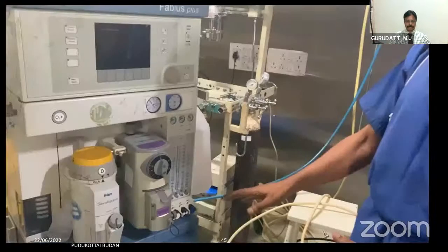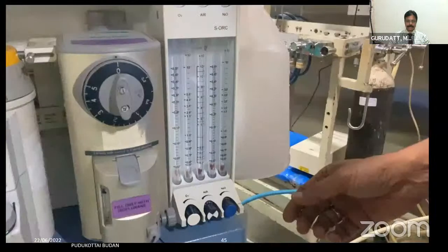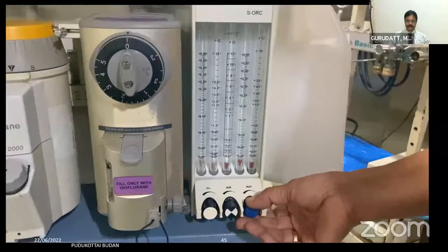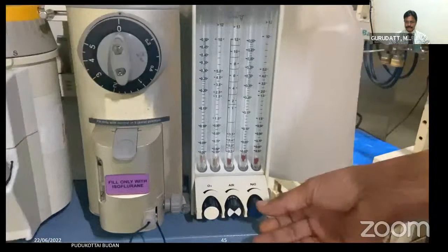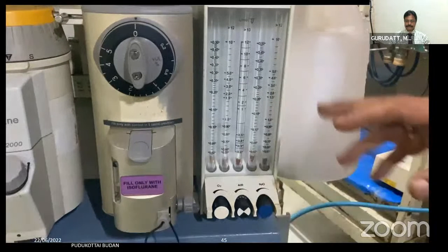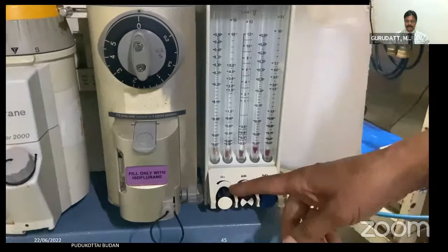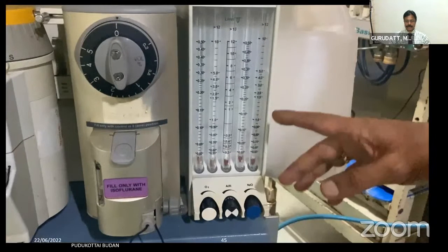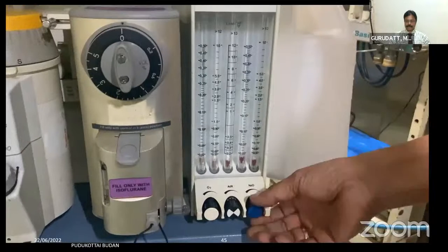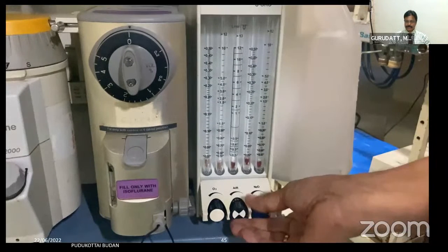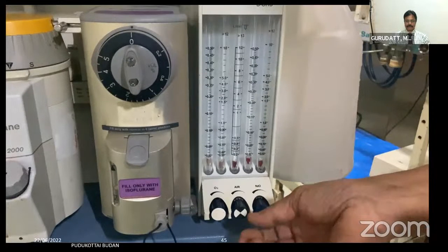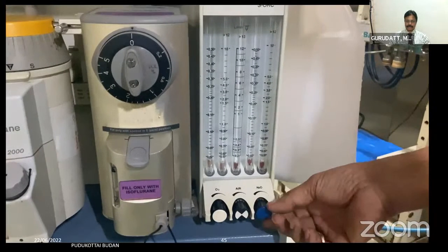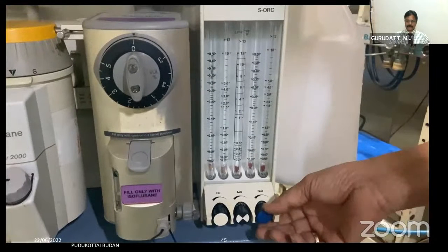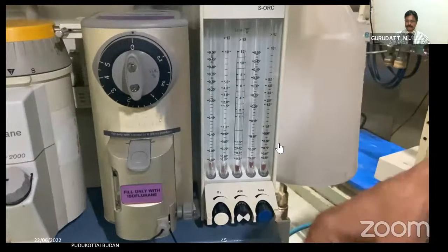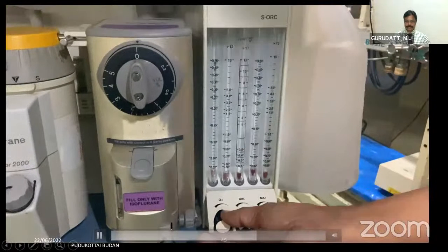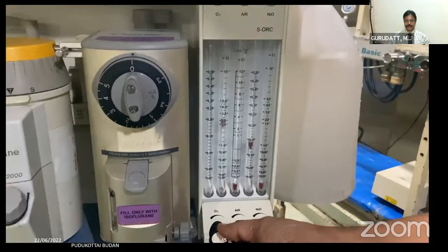So how do we identify whether SORC is there or not? You try to open nitrous oxide. If no flow comes, no oxygen and no nitrous oxide, then it is SORC, because the oxygen has to flow into the nitrous oxide side to open the nitrous oxide in SORC. So the nitrous oxide will not come out when you rotate only the nitrous oxide knob. Unlike in Link-25, where rotating the nitrous oxide knob automatically rotates the oxygen knob because they are mechanically linked. Here I can still give only oxygen, and then the nitrous oxide will not flow.